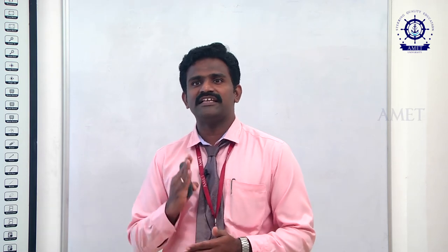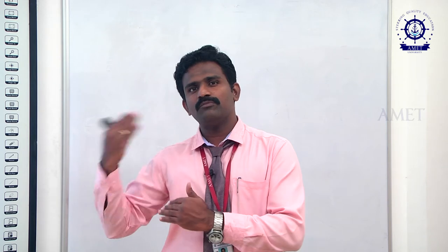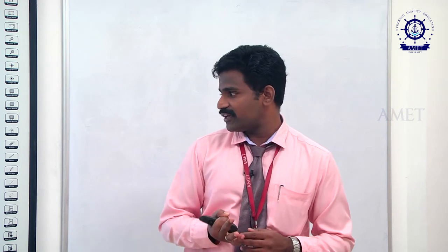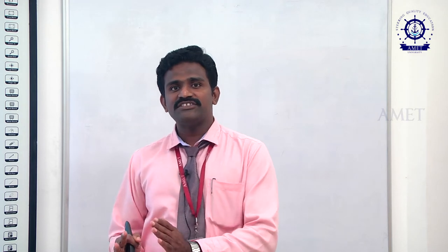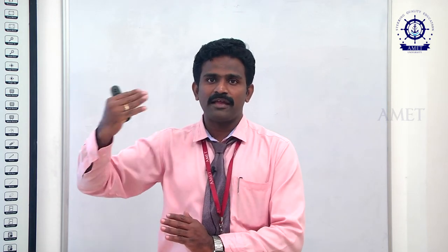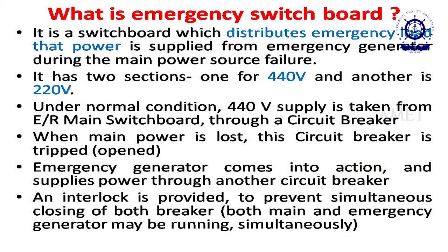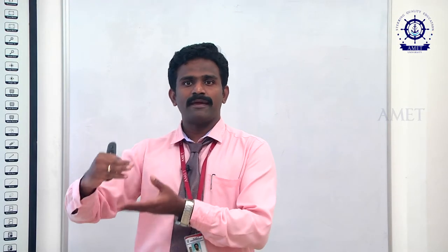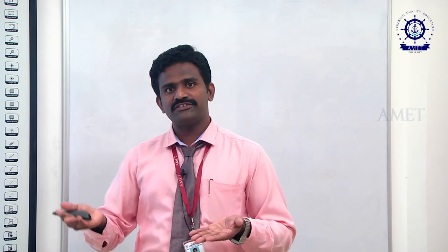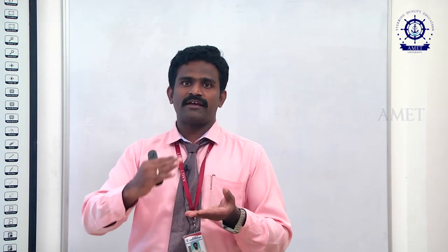The interlock is a very important device connected between the main switchboard and the emergency switchboard. It prevents simultaneous closing of both the main and emergency generator breakers at the same time. When we run the emergency generator in testing condition, the supply from the main switchboard is cut off. Both supplies cannot come to the emergency switchboard simultaneously. That is why we must check and operate the interlock between the two circuit breakers.